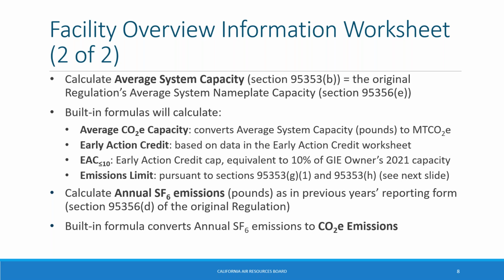Finally, calculate your annual SF6 emissions in pounds as you have in the past, following section 95356D of the original regulation. Once you enter a value, a built-in formula will calculate your CO2e emissions by converting the annual SF6 emissions you entered to units of MTCO2e, so you can directly compare your emissions against your allowable emissions limit in the same unit of measure.